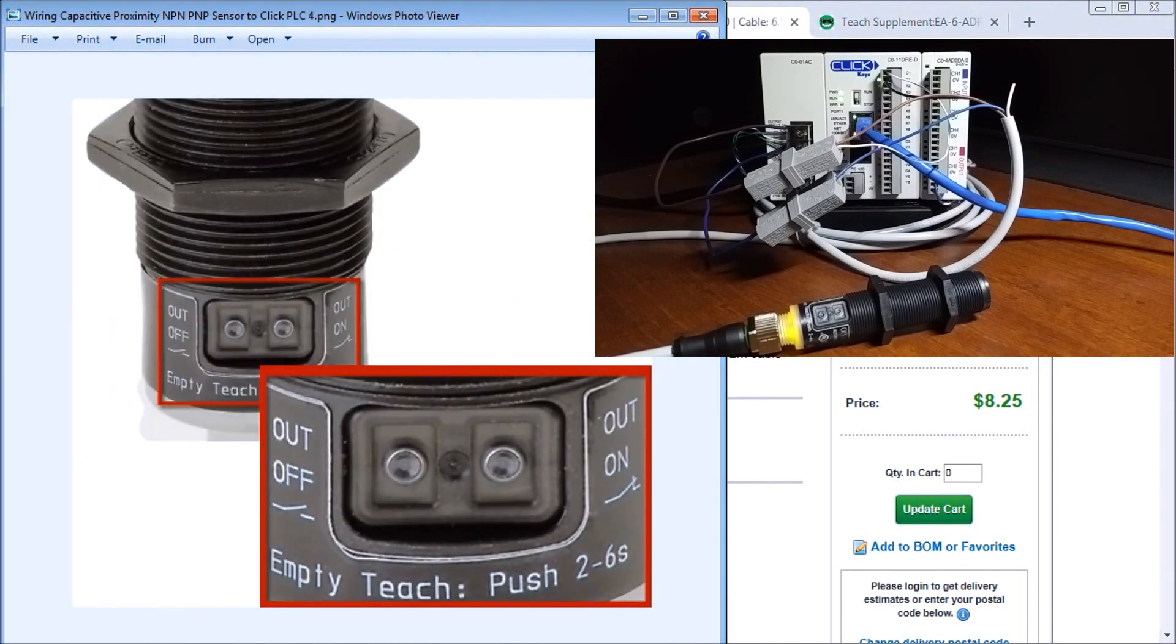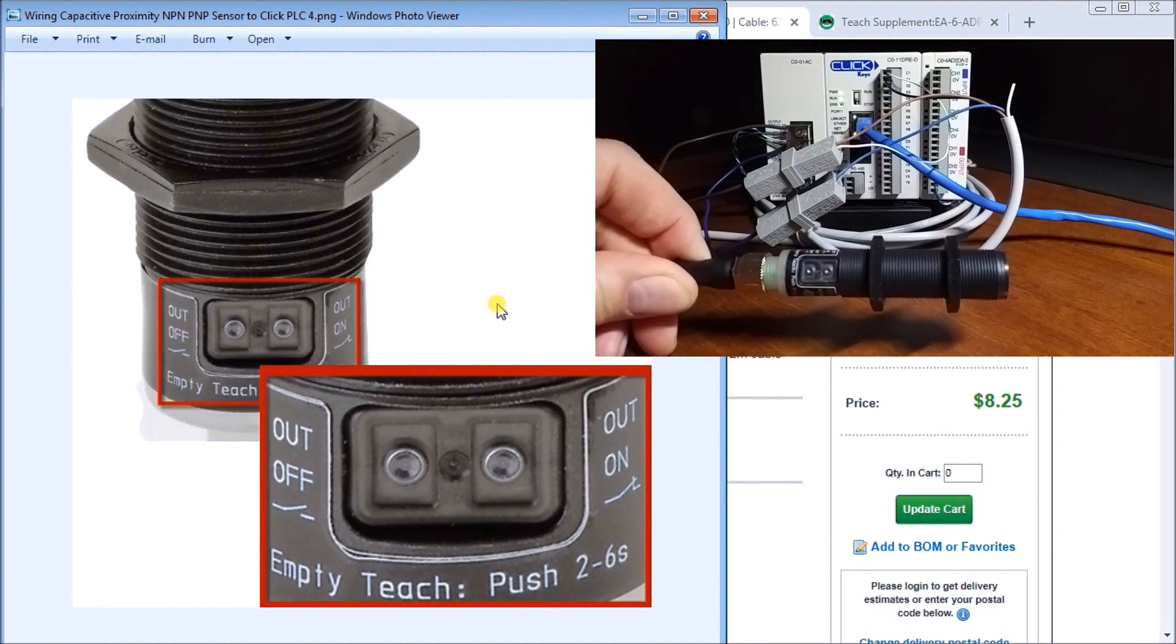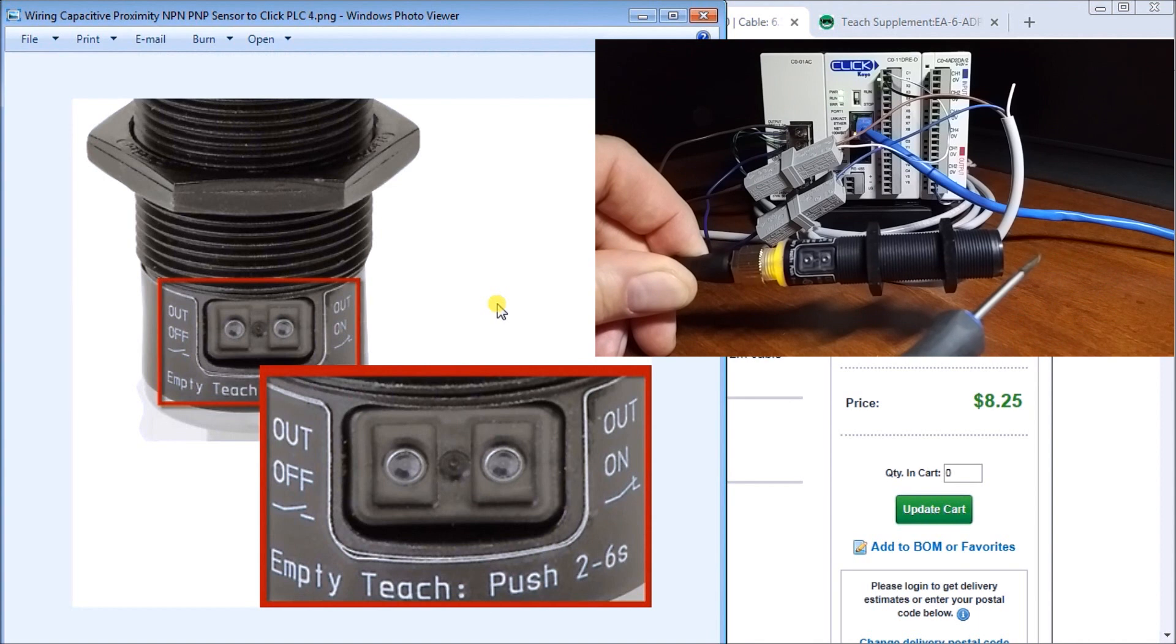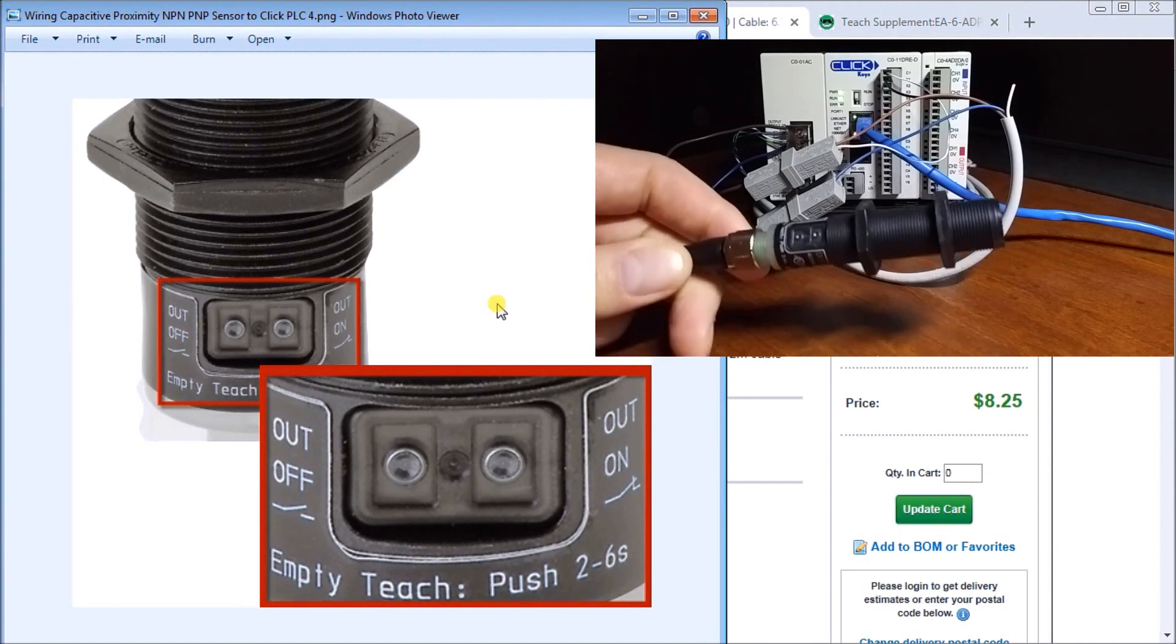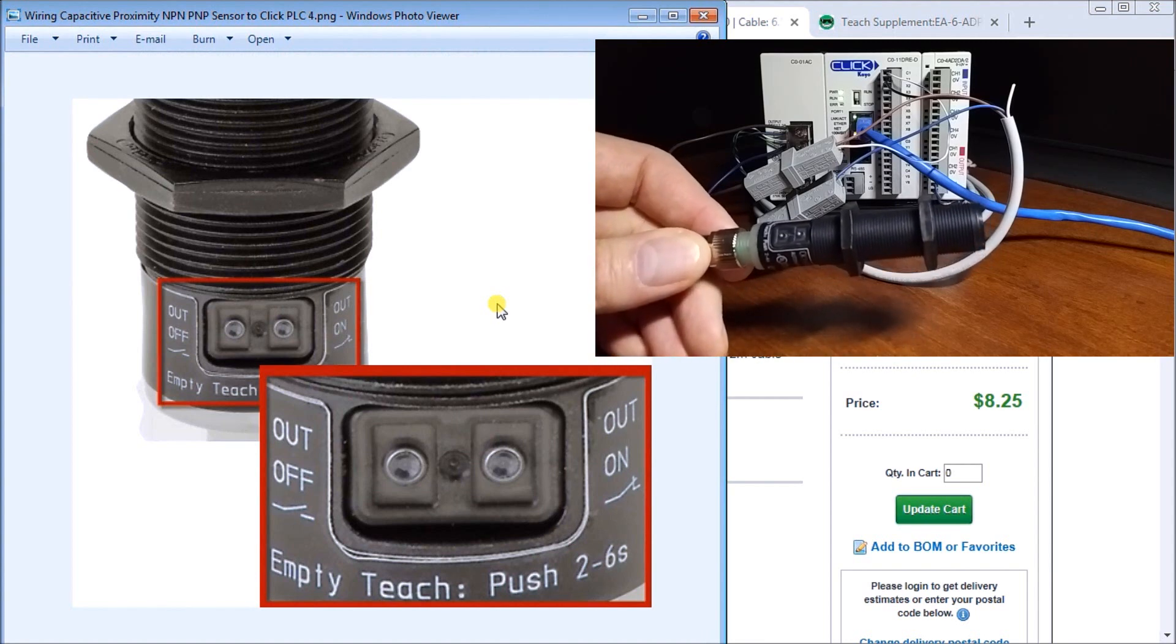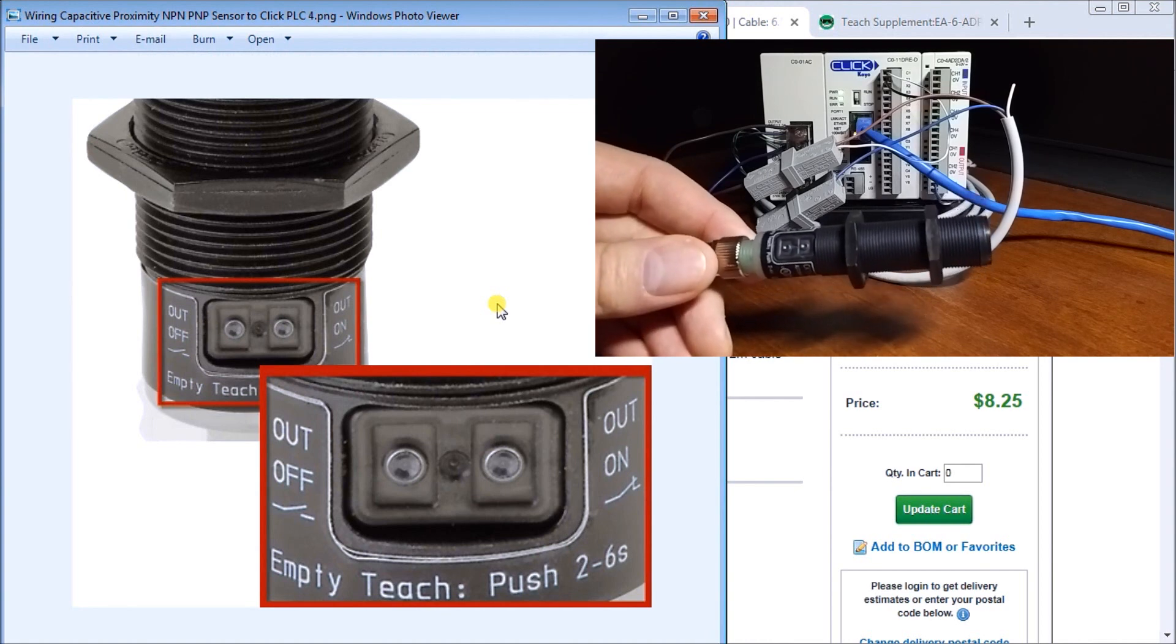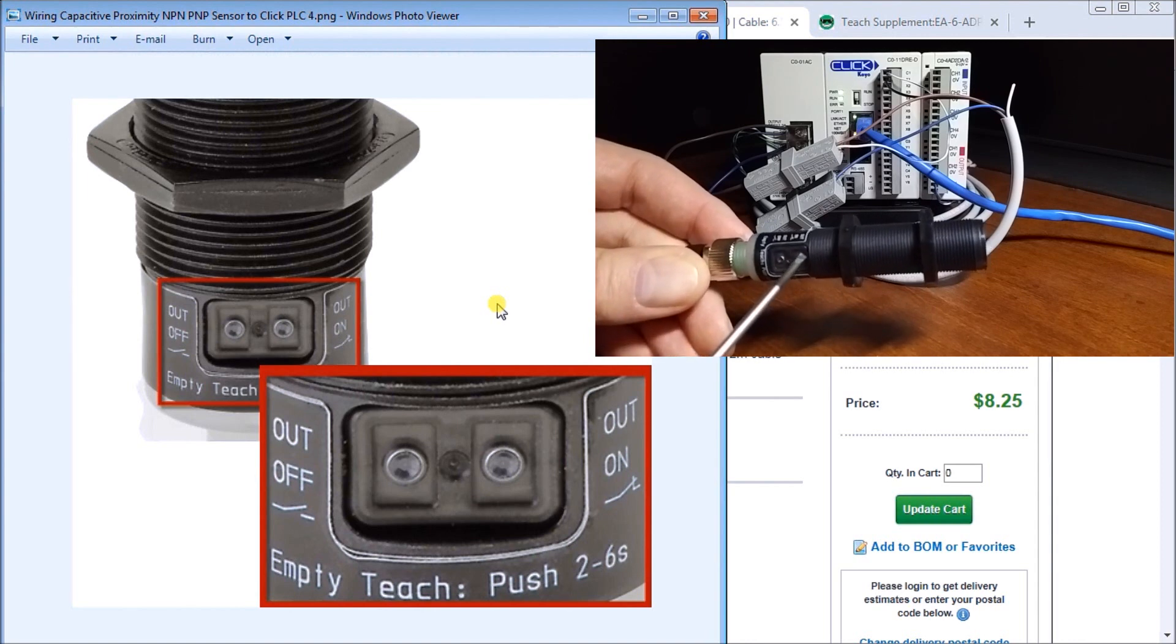Now the next thing is our teach functions and basically right now we have it set so that nothing is detected, it's actually normally open, and then when we detect something it becomes normally closed and completes our circuit. So in order to change that we have two buttons on here and if we hit and hold the button between two and six seconds it will actually change the way that it operates. So right now it's normally open, let's change it normally closed by hitting the out on button.